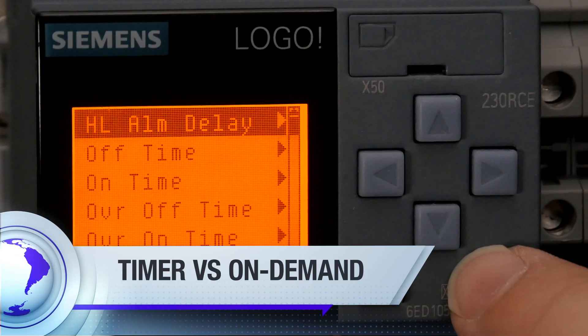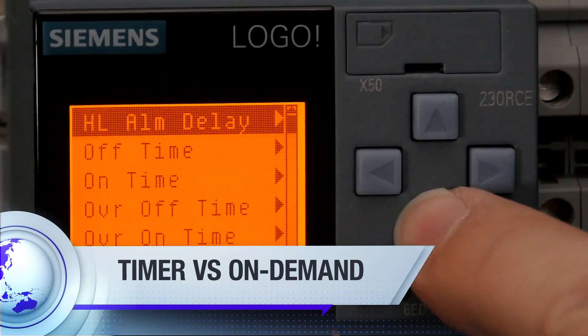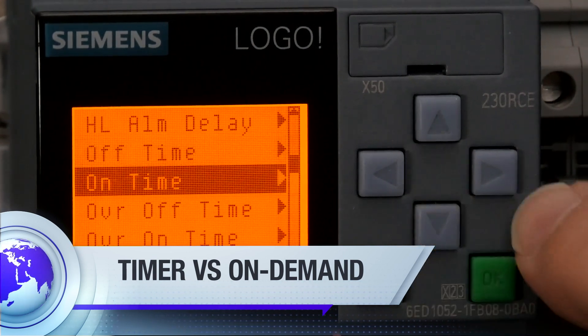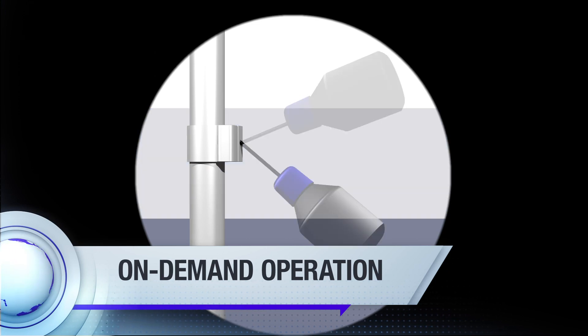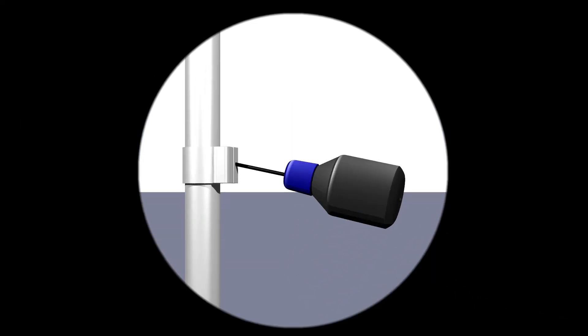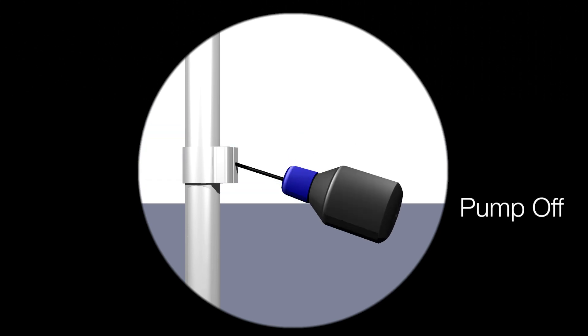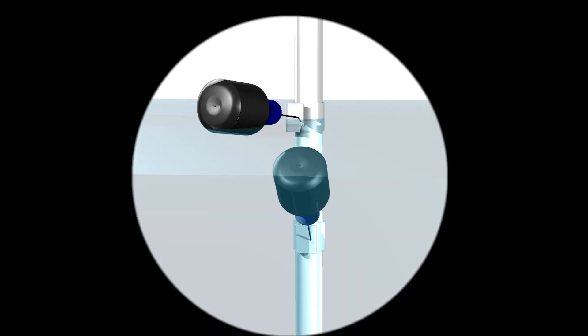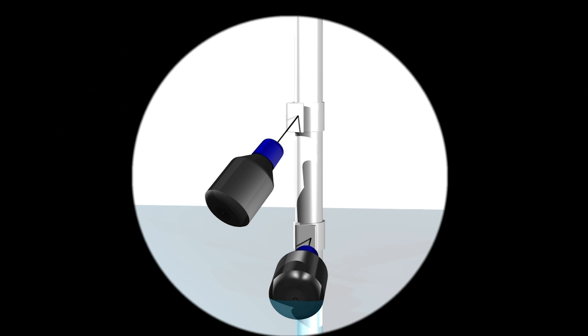Orenco Systems control panels operate in one of two modes: either on-demand pump operation or time dose pump operation. In on-demand operation, the pump will turn on or off based on the position of the pump floats. When the pump on float is in the up position, the pump will energize and will not turn off until the pump off position is reached, or the liquid level in the tank causes the pump off float to reach the down position.